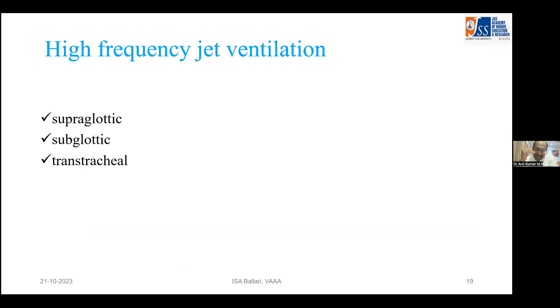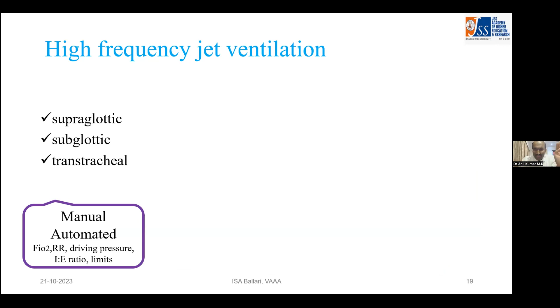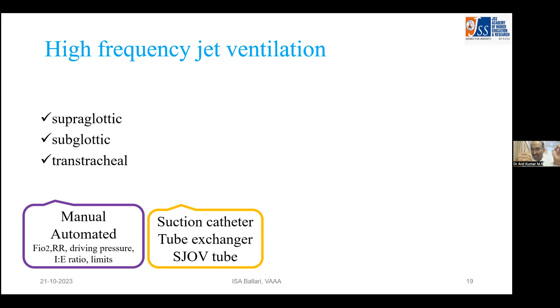The jet ventilation method can be used supraglottically, or by placing the catheter below the vocal cord, subglottic, or through the transtracheal route. The four parameters we are supposed to set are FiO2, respiratory rate, driving pressure ratio, and the alarm limits. If you don't have a dedicated transtracheal catheter, we can use a simple suction catheter routinely available in our operating theater, or a tube exchanger, or the supraglottic jet oxygenation or ventilation tubes.